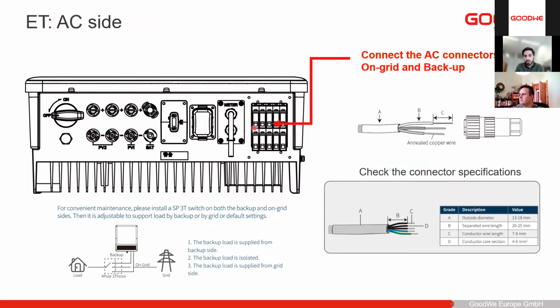On the AC side, as I said before, you need to have the correct cable sizes and connect both the AC to the grid as well as the backup. What we also recommend in some cases, when you go to a place where you want to install the ET but maybe do not have a battery yet, so you cannot use the backup port, or you want to wait with the backup, is that you connect everything and do the proper cabling. But then you can have a 3-pole switch from the backup to the normal grid. And then in the future, when you add the battery, you can just switch some of the loads to the backup output.